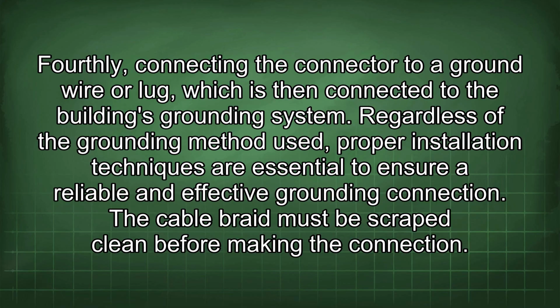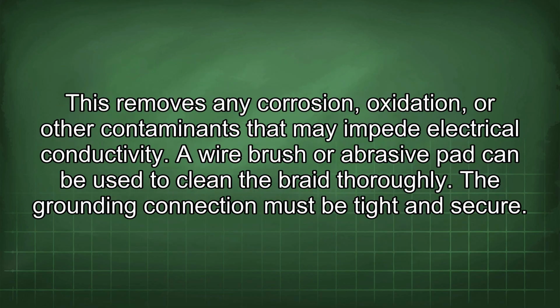Regardless of the grounding method used, proper installation techniques are essential to ensure a reliable and effective grounding connection. The cable braid must be scraped clean before making the connection. This removes any corrosion, oxidation, or other contaminants that may impede electrical conductivity.